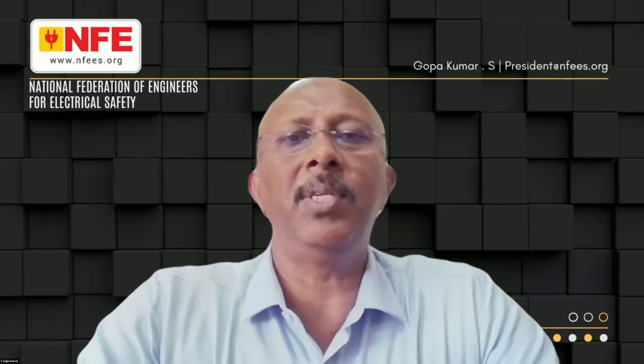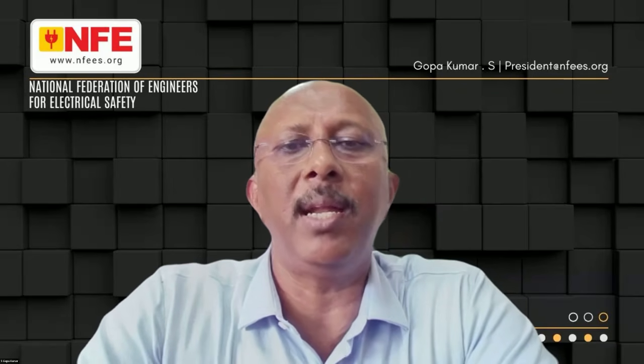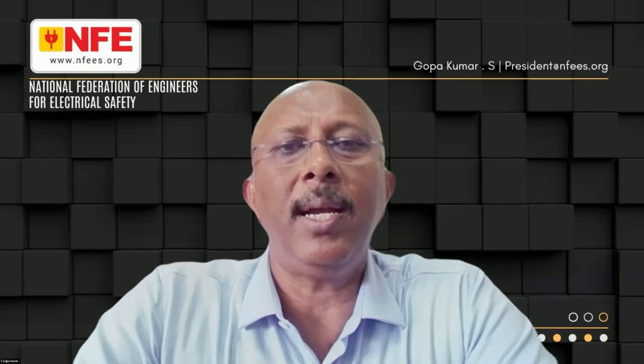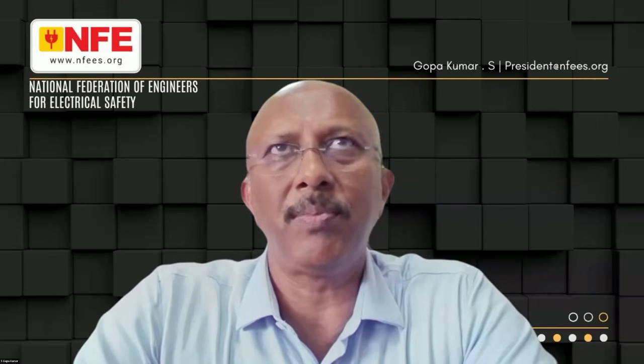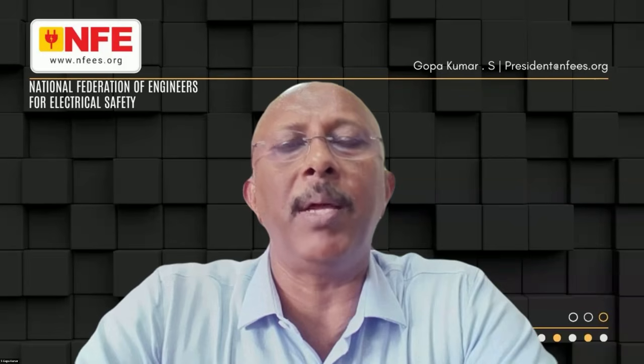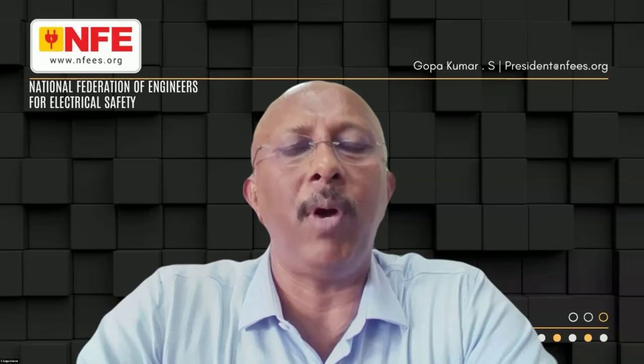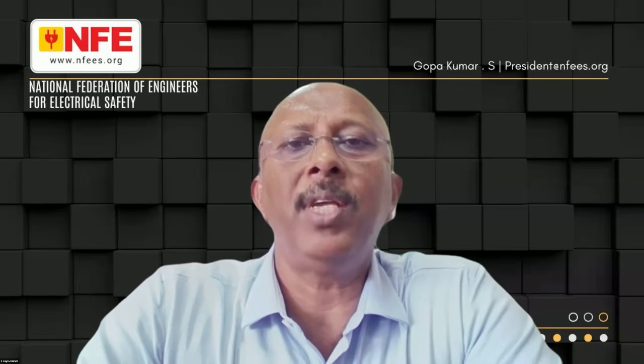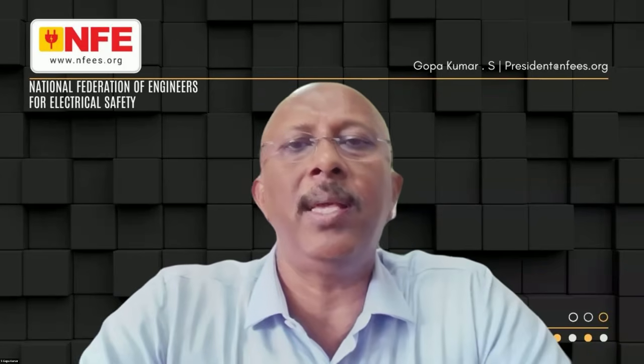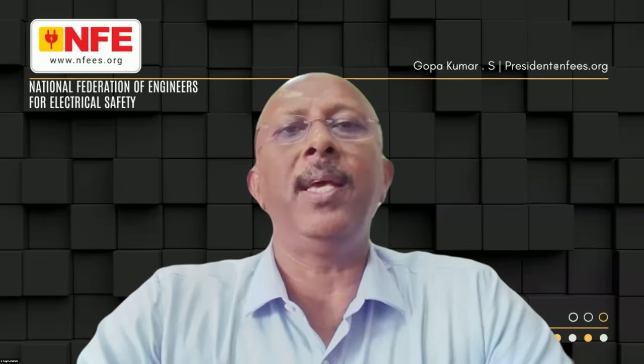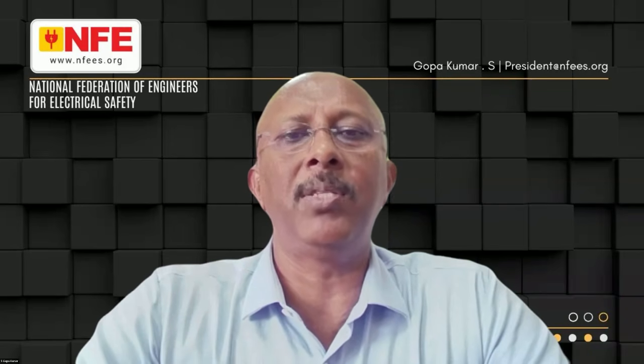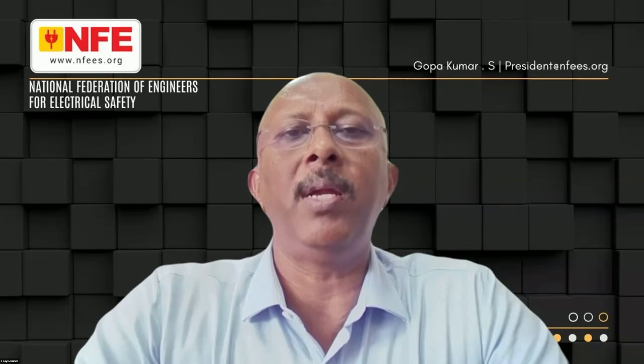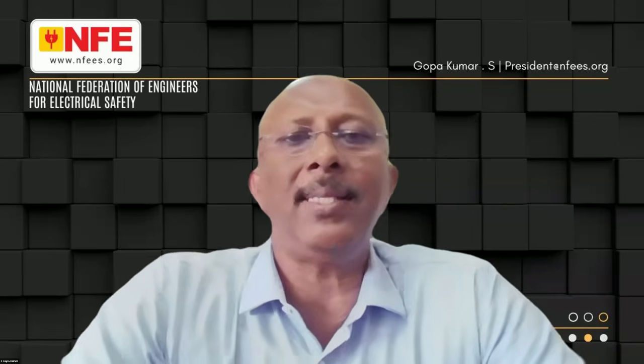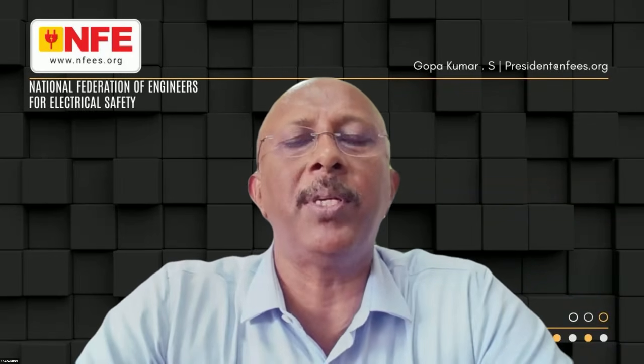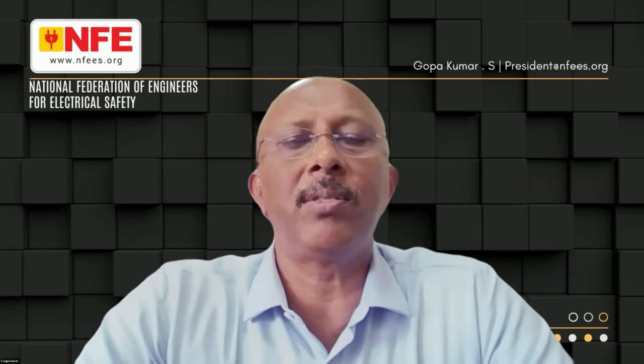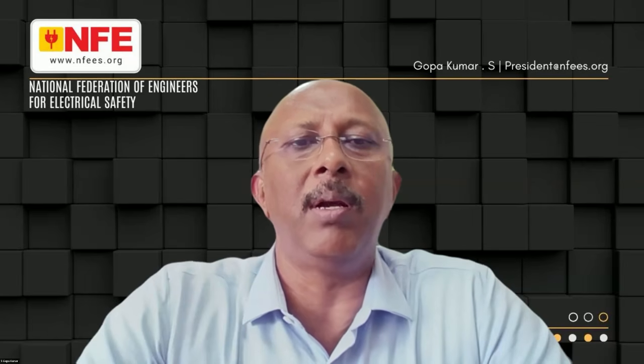EMC is electromagnetic compatibility. EMI is electromagnetic interference. These are high frequency conducted and radiated electromagnetic disturbances, through air or through a copper conductor or wire, during operation of electrical or biomedical equipment. The high frequency can be conducted or radiated, which will destroy the normal operation of nearby equipment. So EMC is basically electromagnetic compatibility. That means once an equipment operates, the nearby equipment should not be disturbed. The classic example in a hospital is the electrocautery machine. Whenever the electrocautery machine works, probably the nearby equipments are in trouble.